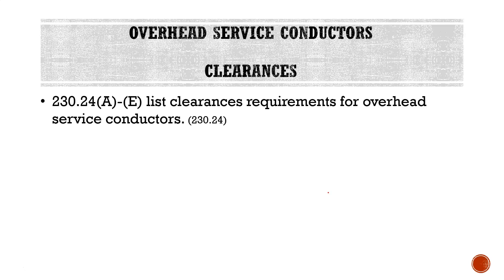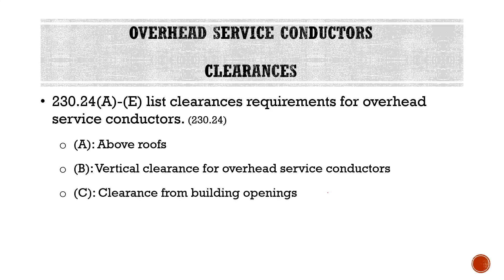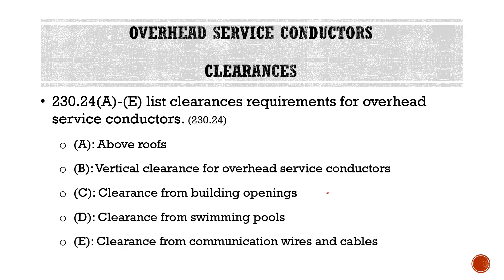Building on that idea, Section 230.24A through E lists clearance requirements for overhead service conductors. Part A covers above roofs; Part B covers vertical clearances for overhead service conductors; Part C covers clearances from building openings; Part D covers clearance from swimming pools; and Part E covers clearance from communication wires and cables.